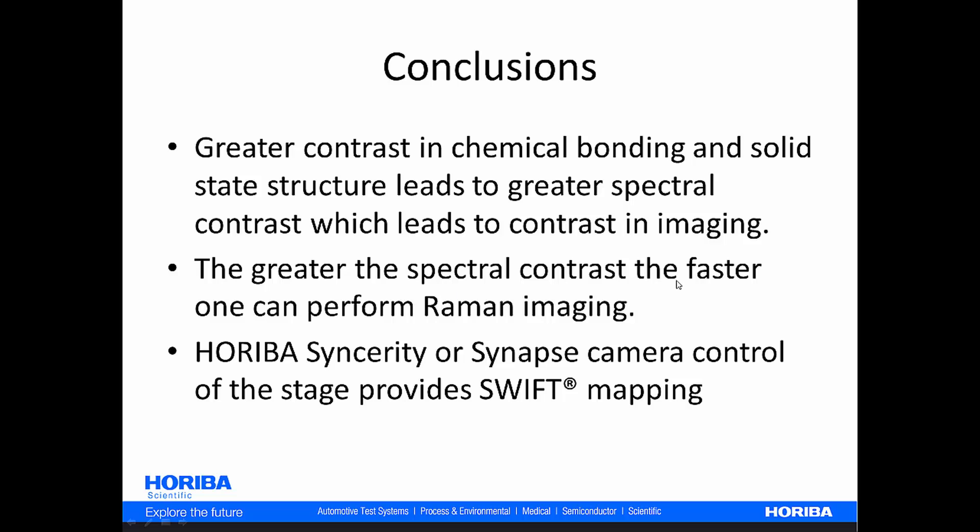And the greater the spectral contrast, the faster one is going to be able to perform that imaging. And finally, the use of SWIFT mapping wherein the Syncerity or the Synapse camera is controlling stage movement and is communicating with the stage such that you have constant stage motion and timing of the camera with the stage motion with the shutter always open, gives you a real significant improvement in your speed for fast Raman imaging.